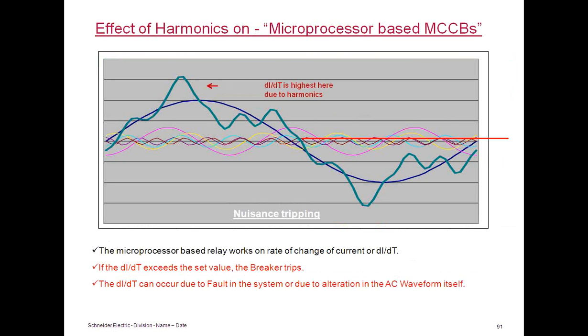So we verified the microprocessor-based circuit breakers operate on something called di/dt, or rate of change of current. So if you look at this waveform here, the blue one is the pure AC, and when you add harmonics to this, you get this waveform which is not a sine wave. So the altered waveform will have a different rate of change at some point of time. If the altered waveform has a steep rate of change of current, then the circuit breaker senses a fault and trips the breaker. So this was happening at this site. So the harmonics adding to the fundamental was creating an artificial fault seen by the microprocessor breaker, and the breaker was tripping frequently. So one tripping is about 1 or 2 hours of downtime, and this is a significant loss for the customer.